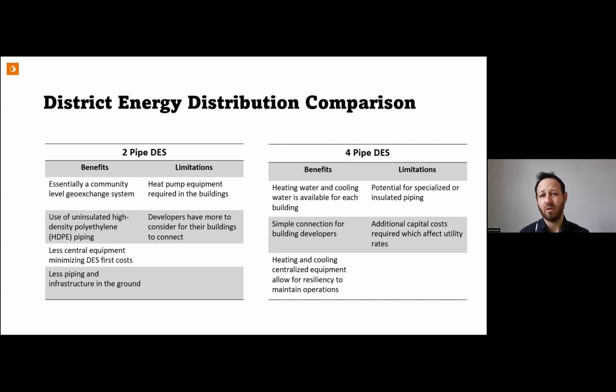But once you go into a four-pipe system, that might lead you into some specialized piping, maybe insulated piping, depending on your temperatures. And because you have four pipes and more centralized equipment, the overall capital cost to create a district system with four pipe is higher upfront. So that's another thing to consider — you're weighing out both sides: a district system that costs more, but buildings that cost less.